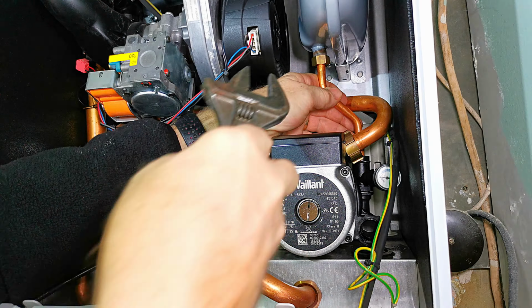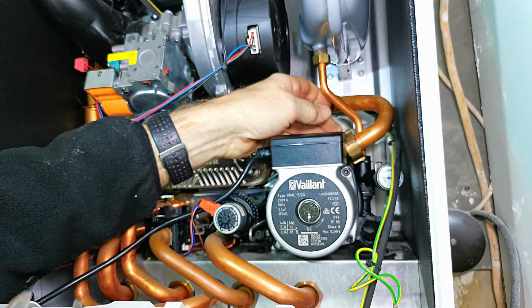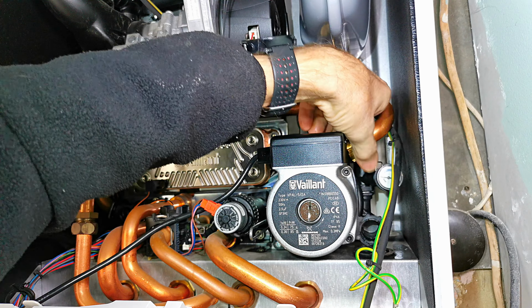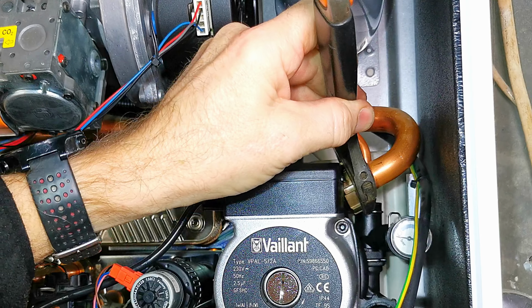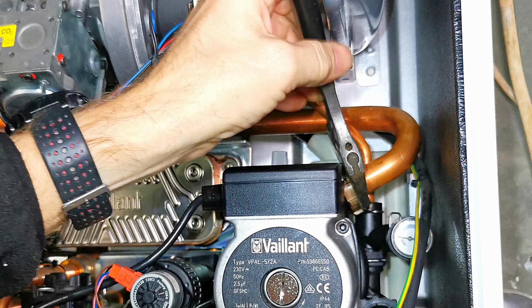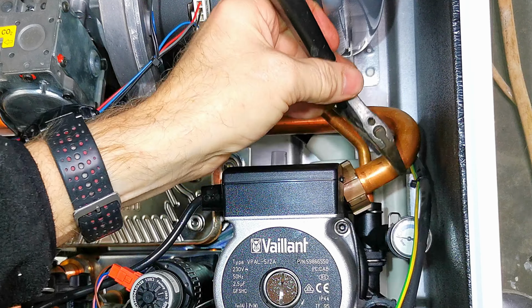When I tighten the nut up onto the expansion vessel, I'd be very careful that the pipe doesn't twist and strain the fittings. So I always hold the pipe and make sure that it doesn't twist. I can then do the nut on the return pipe, remembering not to do this too tight, just need to nip that up. And there we go.